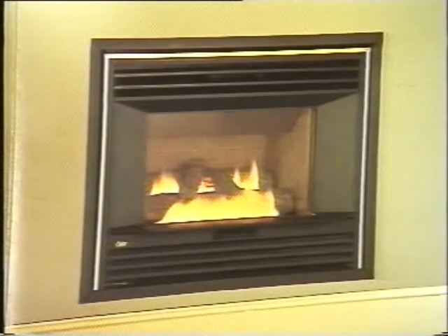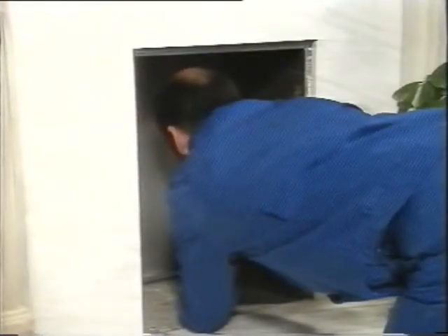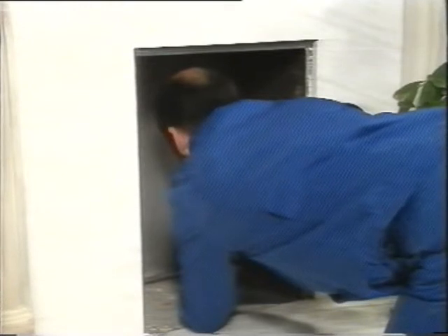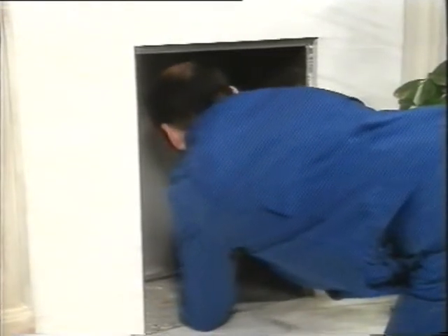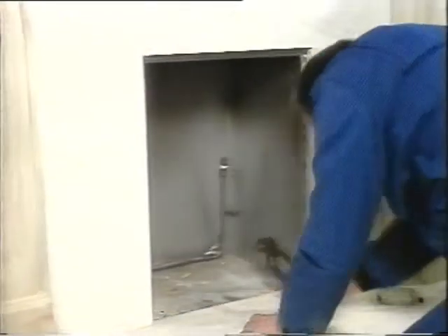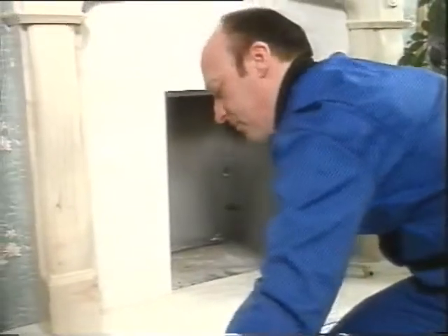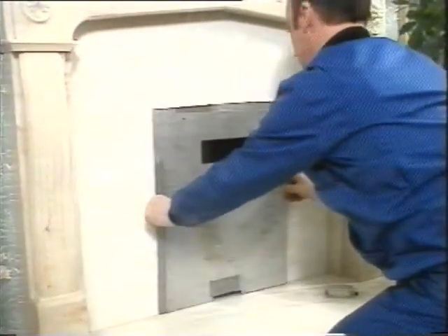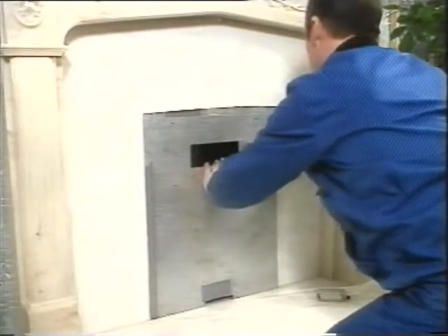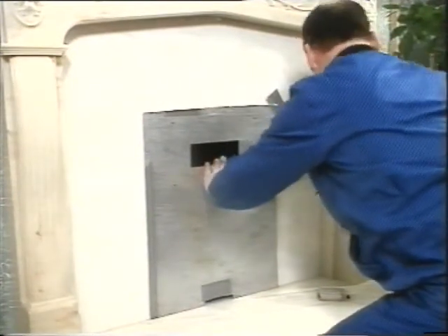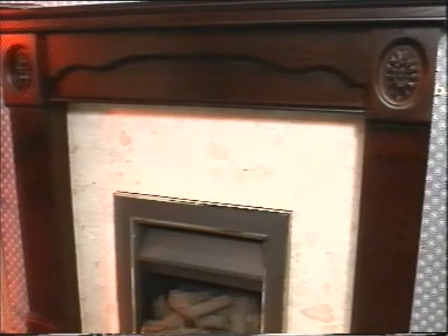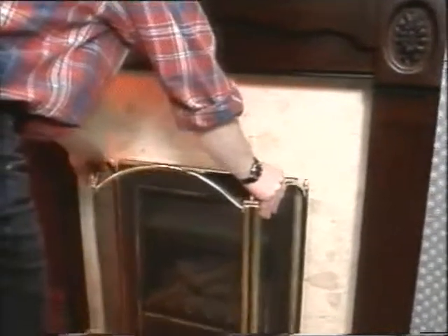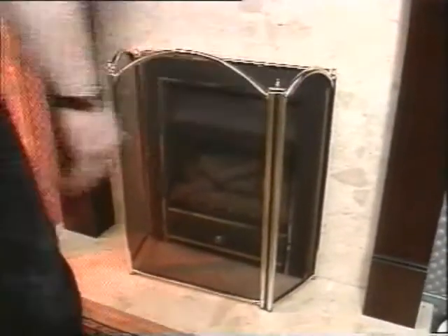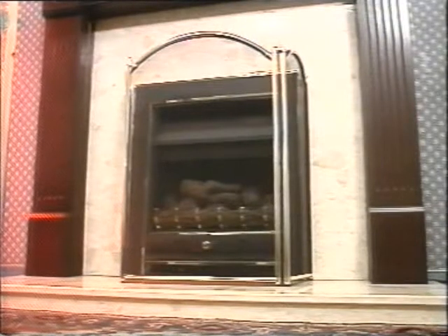Don't ever fit combustible material inside the fire recess. And, as we keep on saying, always check the manufacturer's specific instructions. With precast flue block chimneys, this is crucial because some manufacturers advise against fitting their products in such locations. And, of course, it's common sense to tell the customer to use a fire guard, especially if there are going to be children, elderly, or infirm people near it. Make sure that the guard they use conforms to BS regulations.